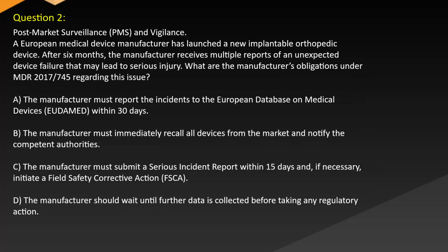Question 2. Post-market surveillance (PMS) and vigilance. The European medical device manufacturer has launched a new implantable orthopedic device. After 6 months, the manufacturer receives multiple reports of an unexpected device failure that may lead to serious injury. What are the manufacturer's obligations under MDR 2017-745 regarding this issue? A.